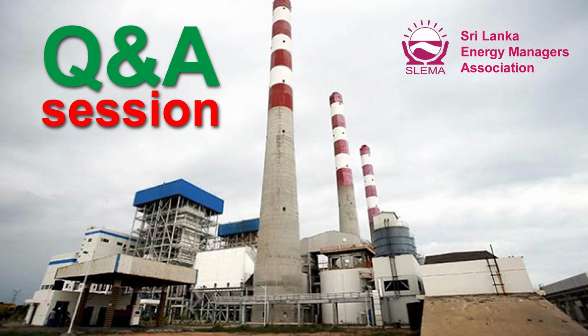It's only that there were many constraints over the last decade. The power plant is 10 years old. There were many constraints, including financial constraints, that prevented the solution from being implemented. So, of course, the recent blackout and what happened to the power plant became another reason to examine and make final decisions on the solutions. If it is a fast cutback situation where the power plant moves to house load, then obviously without any disruption, if there is a source of auxiliary power, it can be switched on, synchronized to the 6 kV bus bar of the power plant, and then the power plant can be brought down to a safe shutdown so that it remains hot to be restarted and loaded when the grid comes back. So that's of course an easy solution.